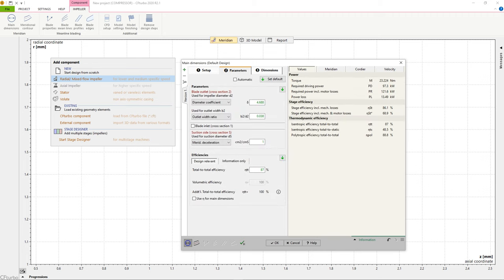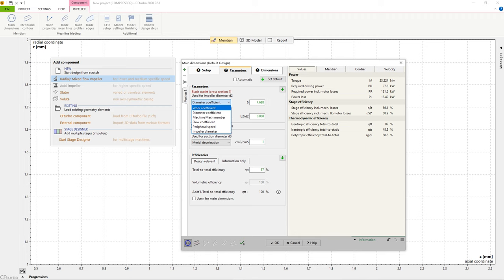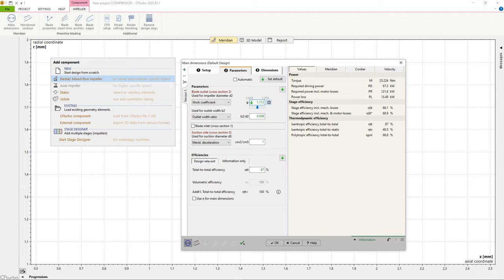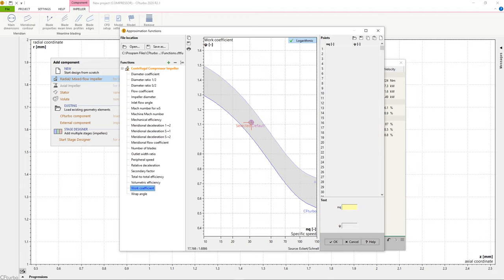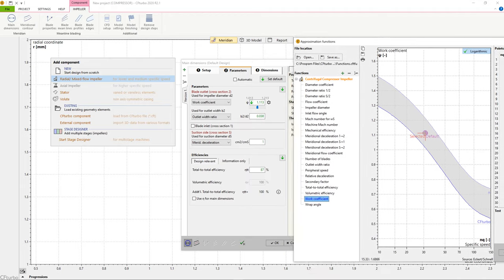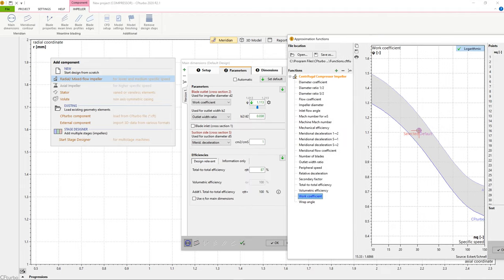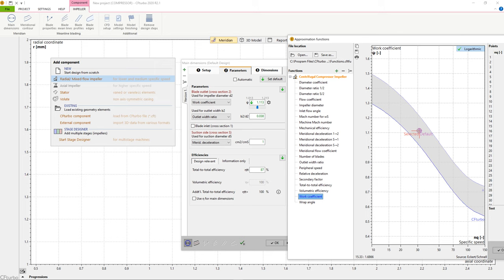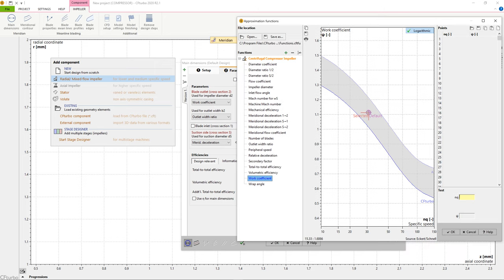In the parameters section, we can select empirical function to design reasonable impeller main dimensions from the very beginning. In this example, we use correlations for work coefficient, diameter ratio, and meridional deceleration. An estimate for the efficiency is required as well.